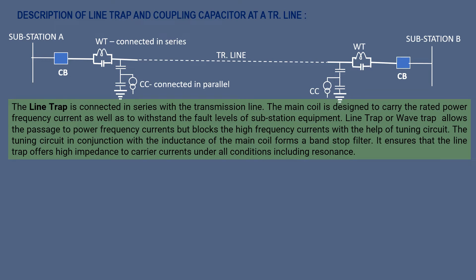The line trap is connected in series with the transmission line. The main coil is designed to carry the rated power frequency current as well as to withstand the fault level of the substation equipment. The line trap or wave trap allows the passage of power frequency current but blocks the high frequency currents with the help of a tuning circuit.